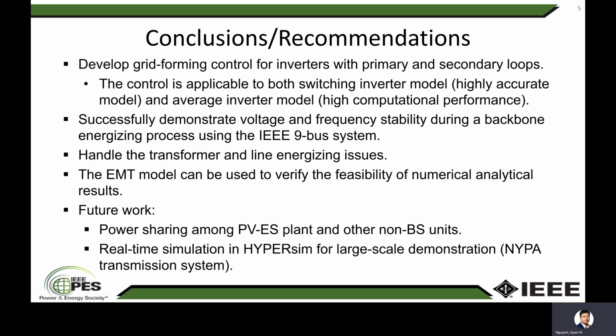In conclusion, in this work, we developed grid forming control for inverters with primary and secondary control loops. The control is applicable for both switching model and average model of inverter. We were able to demonstrate the voltage and frequency stability during the entire backbone energizing process using an IEEE nine-bus system. We were able to find a solution to handle the transformer and line energizing inrush current issues. And we believe that the grid forming model that we developed in this work can be used to verify the feasibility of numerical analytical results, for example, from a power flow or optimal power flow studies.